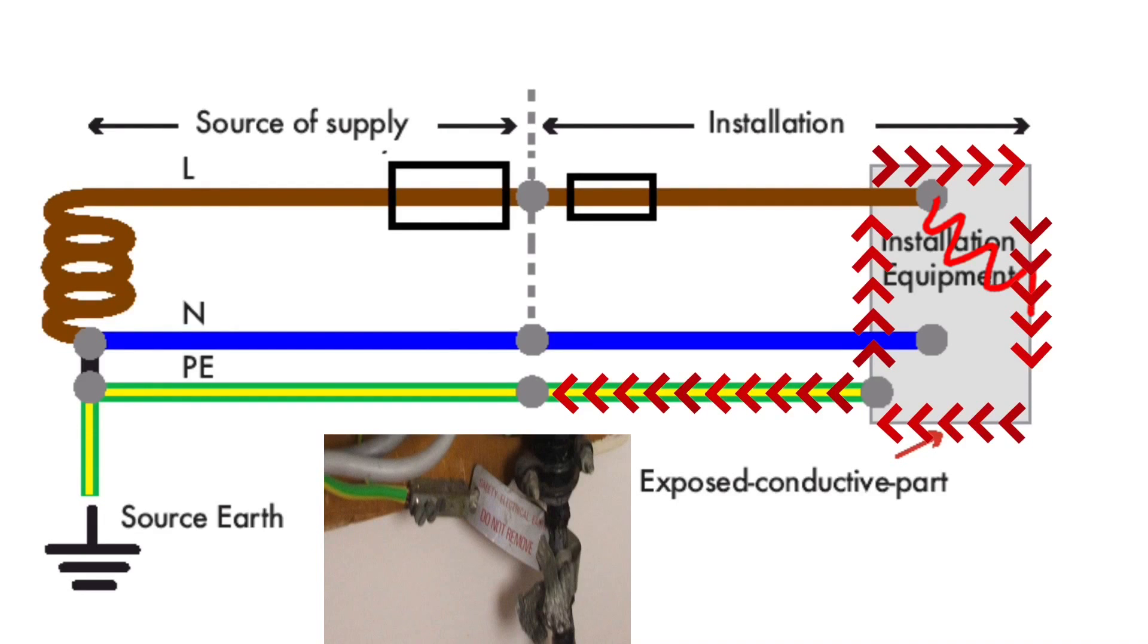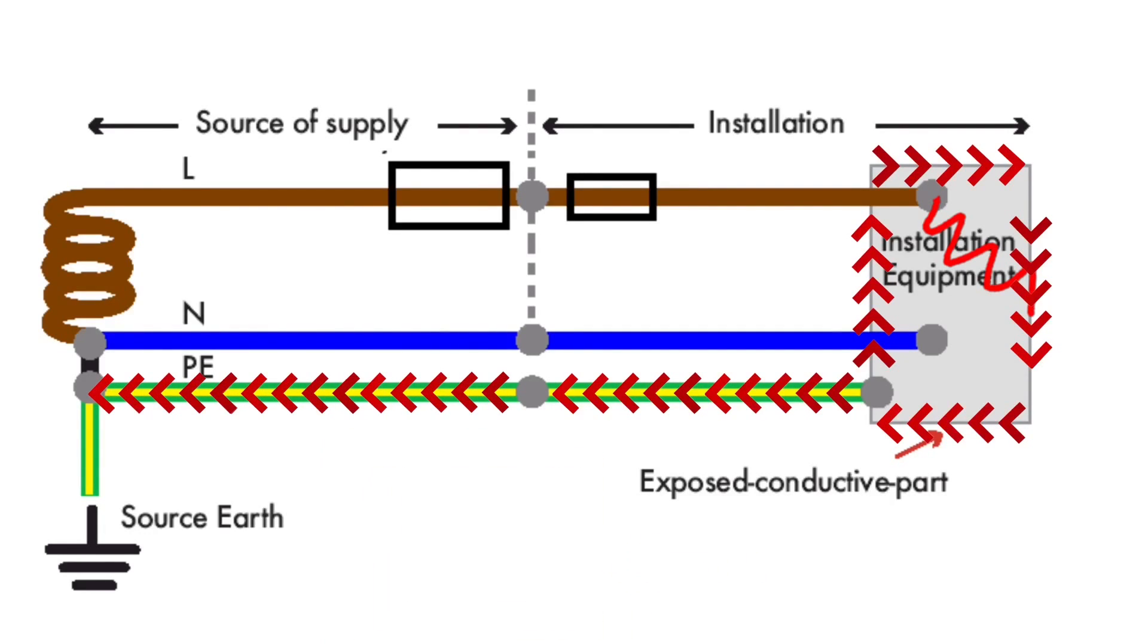The earthing conductor is connected to the lead or steel sheath of the supply authorities cable which becomes live. This is connected to the earth neutral point within the transformer which becomes live back round the line conductor completing the circuit.